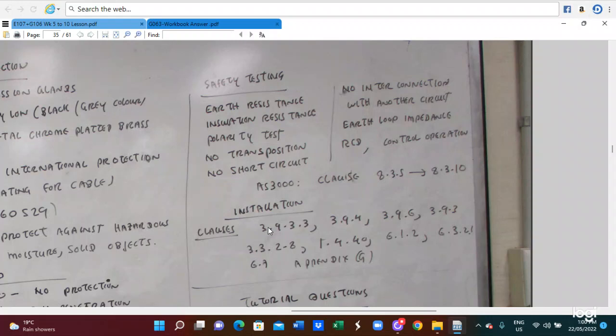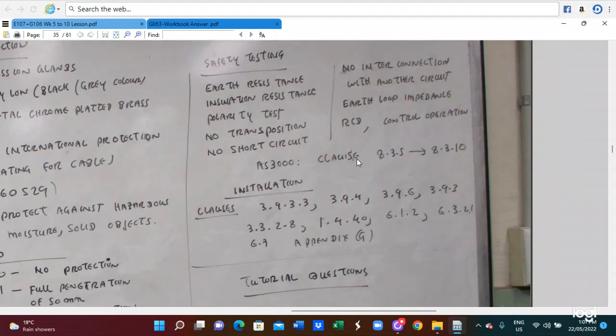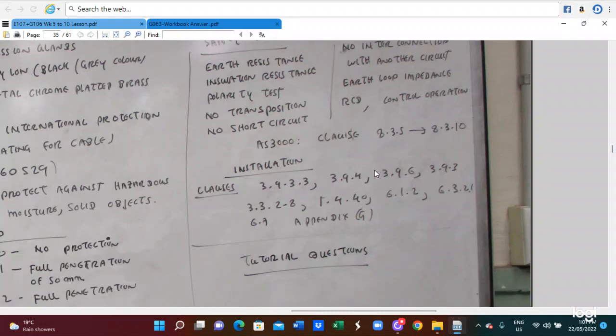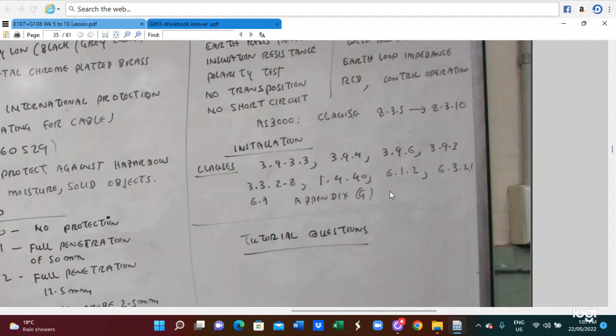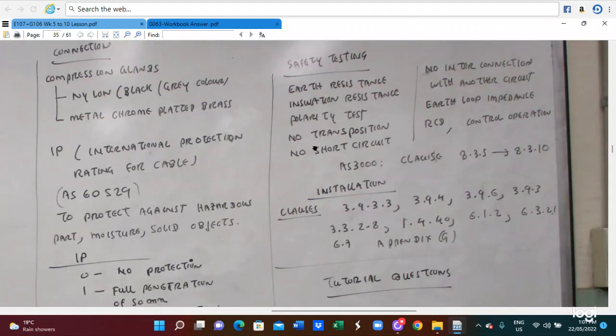We also need to do the safety testing. We have to measure the insulation of the system, polarity test, no transposition, no short circuit, no interconnection with another circuit, and earth loop impedance, RCD, and the control operation. AS/NZS 3000, clause 8.3.5 to 8.3.10 need to be followed. Regarding the installation, AS/NZS 3000, clauses 3.9.3.3, 3.9.4, 3.9.6, 3.9.3, 3.3.2.8, 1.4.40, 6.1.2, 6.3.2.1, 6.7, and Appendix G need to be followed. So those are the connection and the safety protection.